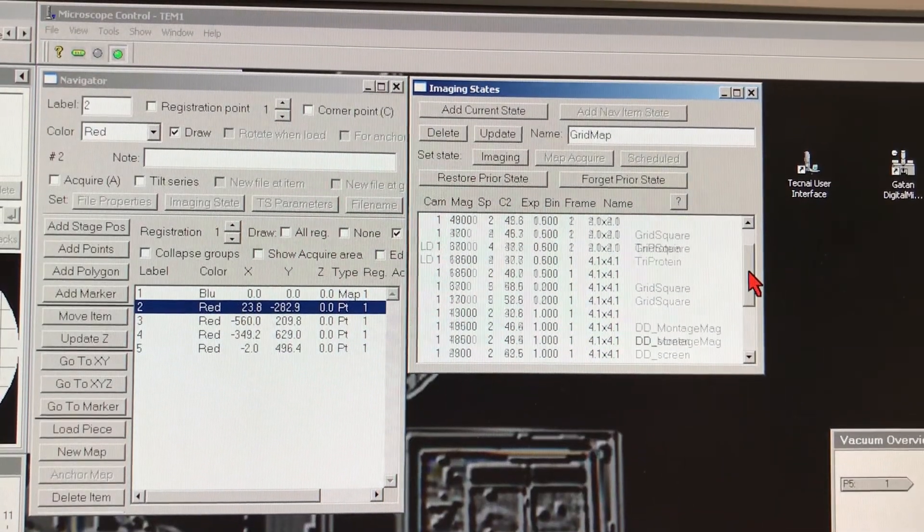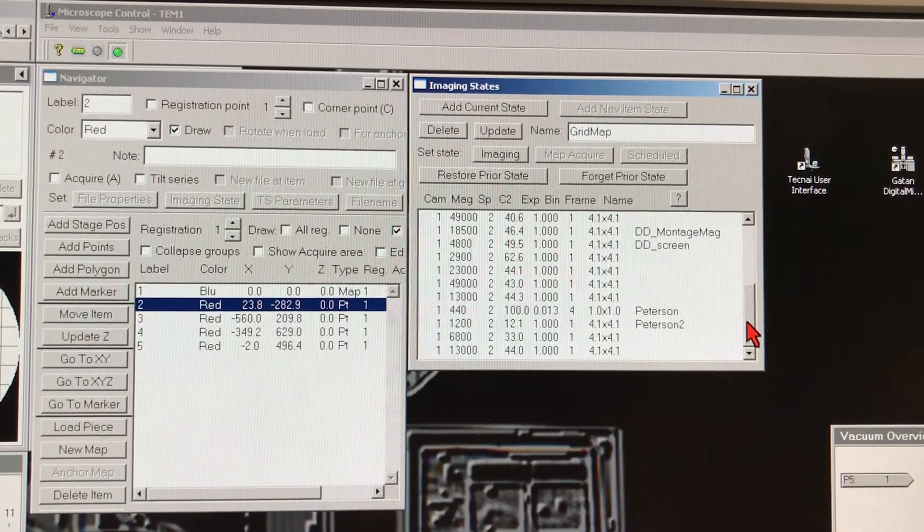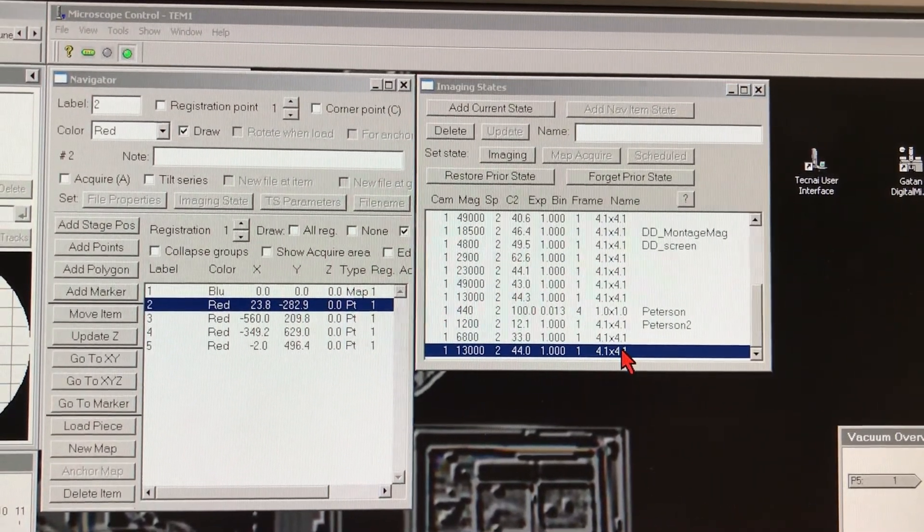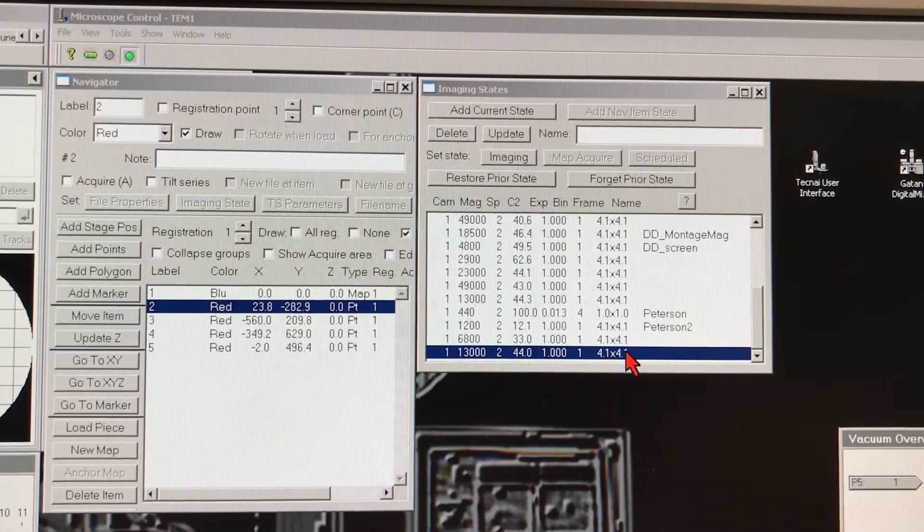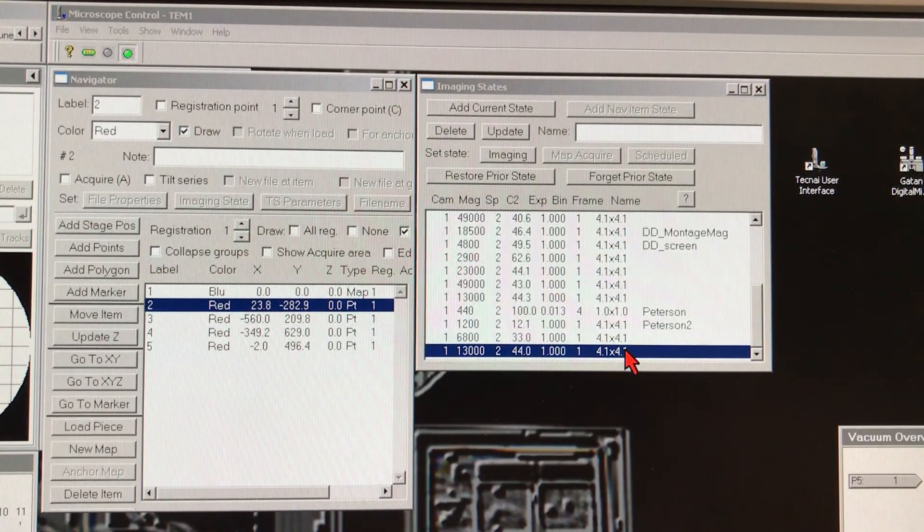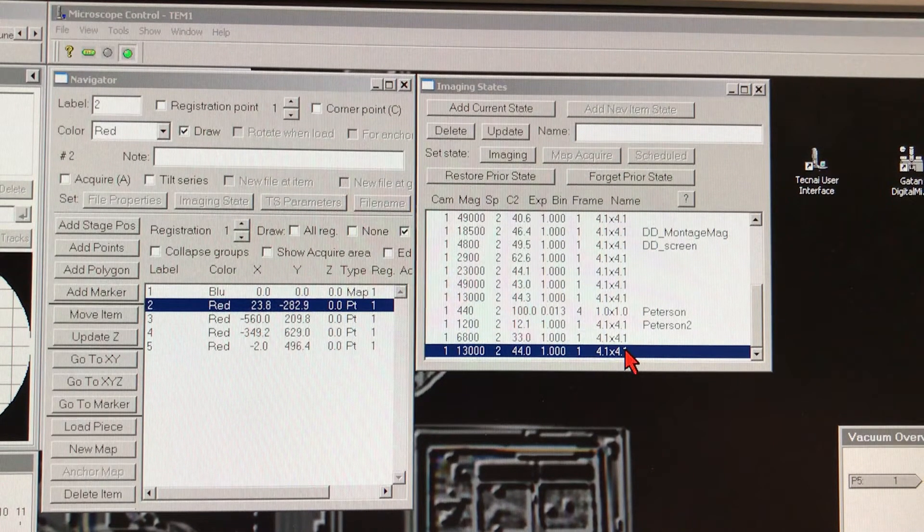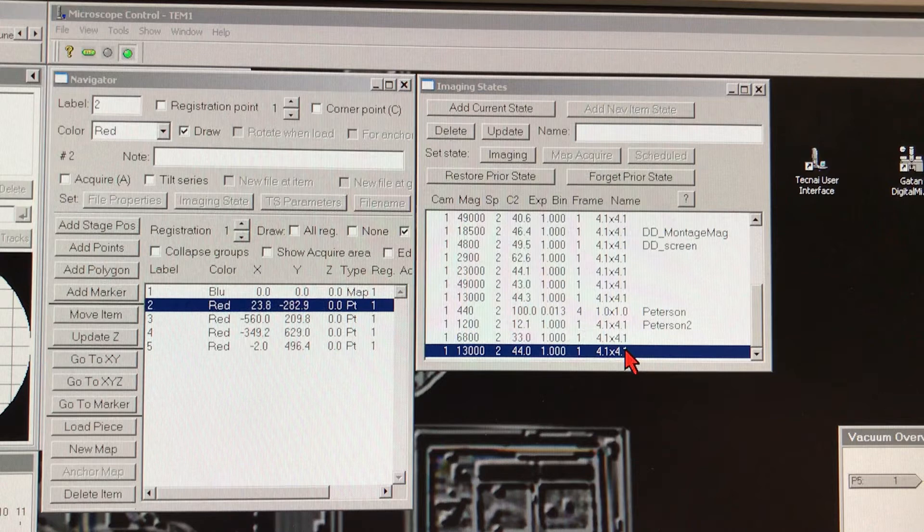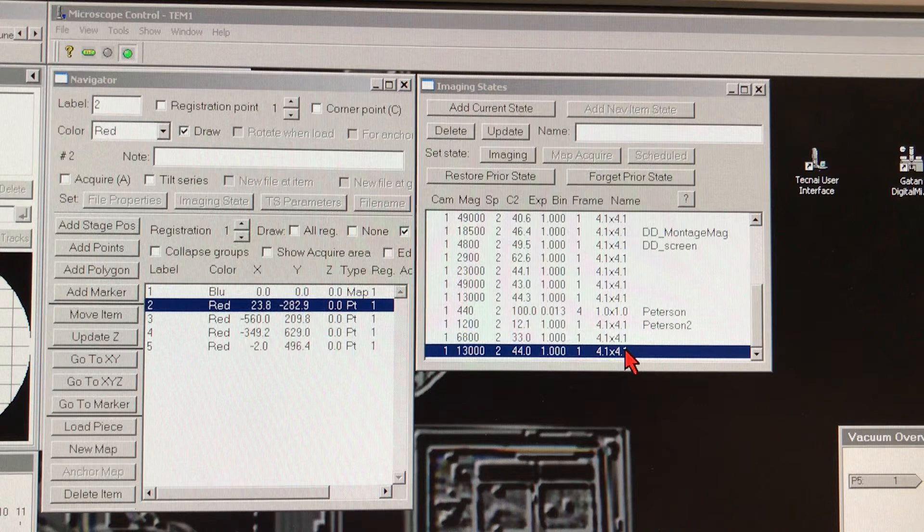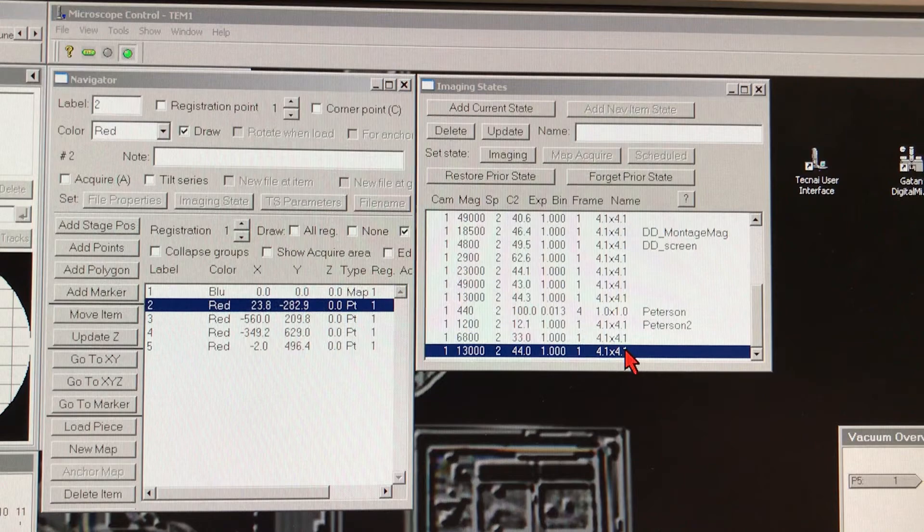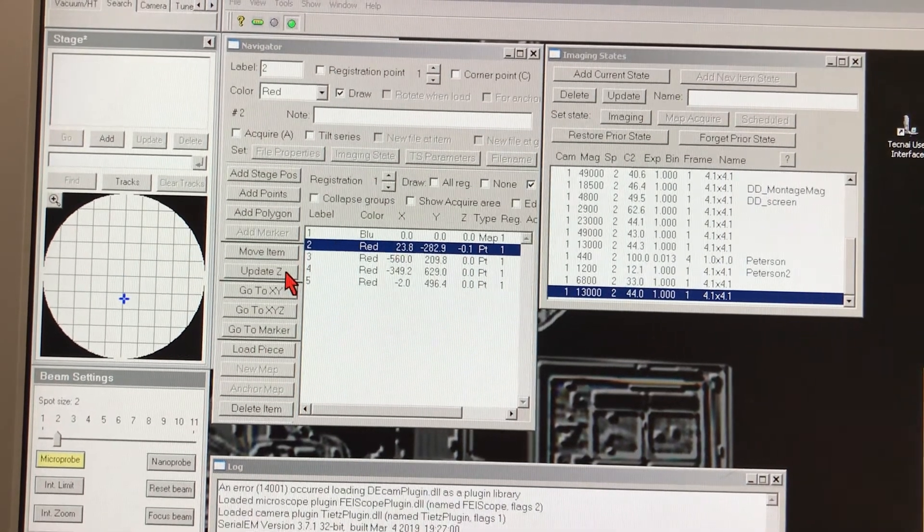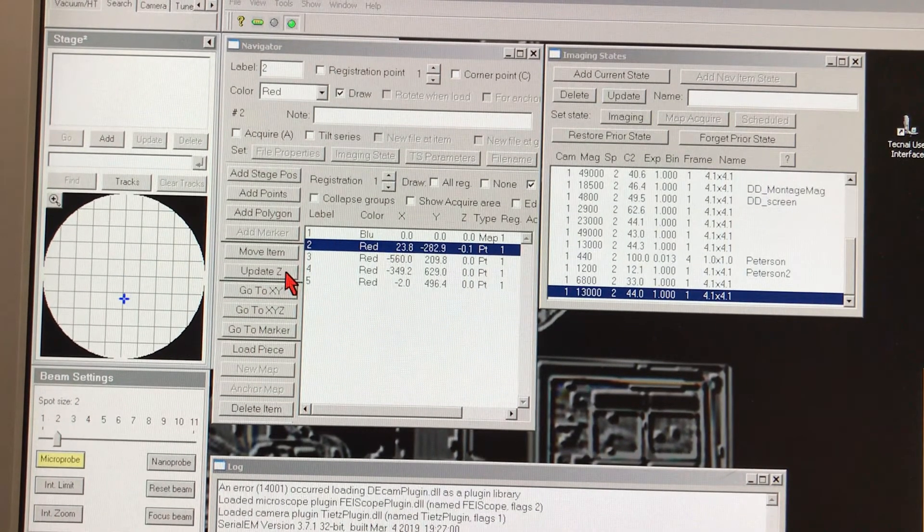Now that we have our areas of interest, the next thing we're going to do is go to the imaging states of the SerialEM software and scroll down to a magnification that is pre-set up. You can also do this manually using the control knobs on the microscope, but the beauty of this program is that you can save the imaging condition settings and quickly go back to the settings whenever you come next time for imaging. Now that we have the right magnification and setup, we are ready to go to the area of interest, which is in this case position 2 that we saved. Using the Go to XY button on the Navigator, we will ask the software to take us to the coordinates that are highlighted here in blue.